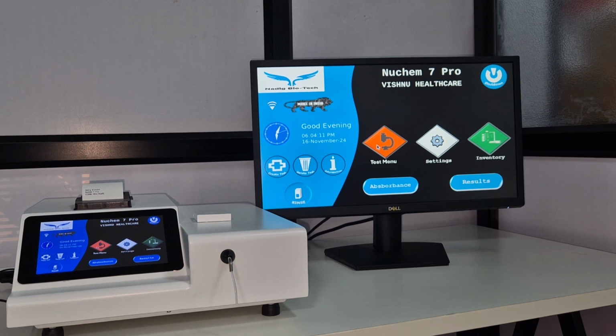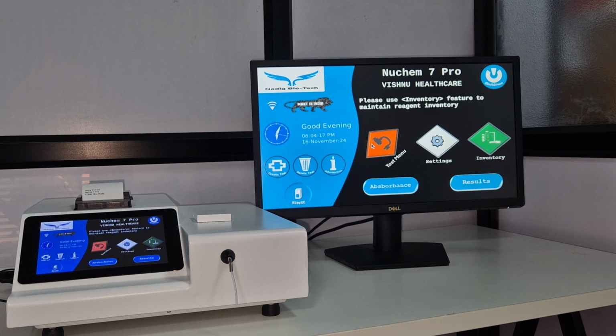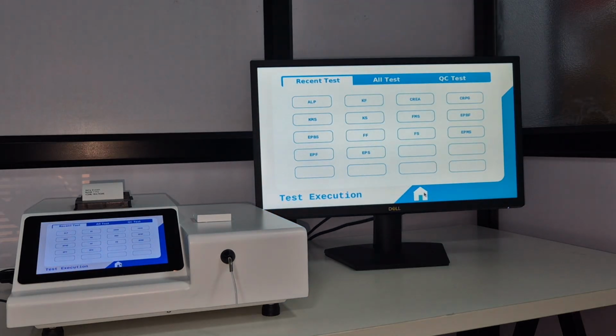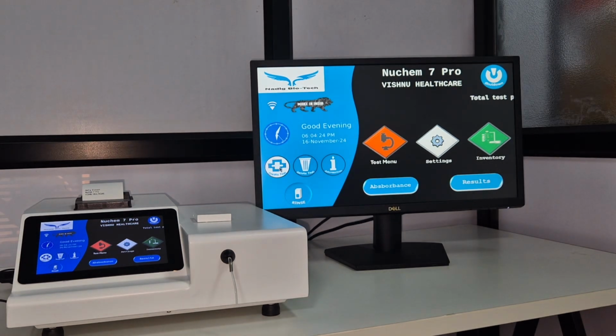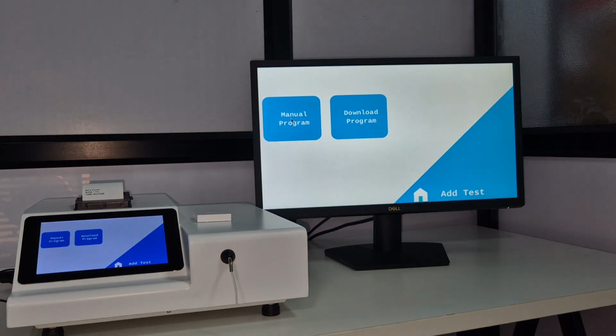The technician will also be able to program this instrument using Wi-Fi, in the sense that for any new kit he buys, when he wants to add a new test, he can either do it manually or by using download program. By doing this, he has to enter the reagent code which will be provided by the reagent supplier. Once this code is entered, it sends the code to the central web server, which sends the parameters back to the instrument. The instrument receives the test parameters, programs them and installs them. So the hassles of programming can also be avoided.